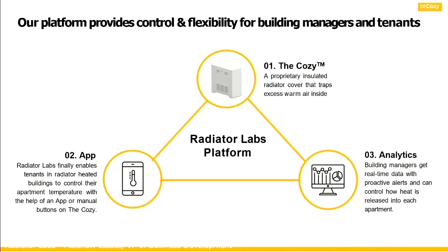The system as a whole includes that thermostatic radiator enclosure with the sensor that measures radiator temperature and room temperature, an app where residents can schedule their temperature, but they can also walk right up to the cover themselves and turn the temperature up or down, and then an analytics platform where all the data coming out of the room temperature, radiator temperature, and steam trap temperature that we're measuring gets sent to the cloud and then in turn sent to the boiler controller of a building.